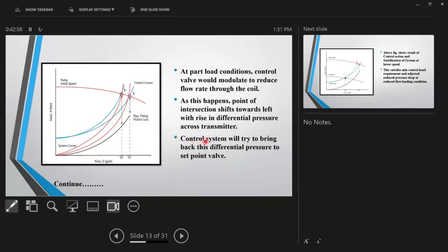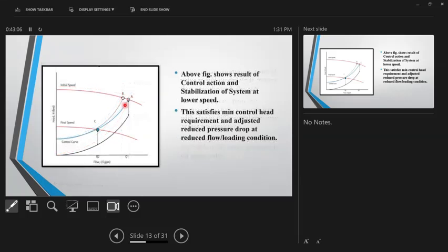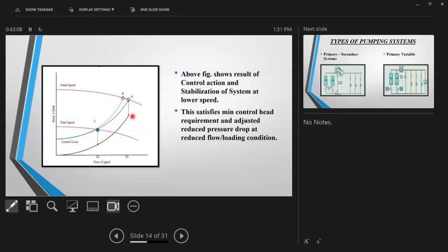But again, we all know the control system will try everything to bring this differential pressure back to set point value. So what it does finally, it does like this. This was our initial point. We thought it would go here, but it can't happen. Now what actually happens is, you remember the control curve, it will follow the control curve, and the final speed will be settled at a point where your flow is satisfied and this distance is equal to this distance. Where that happens, that's the final speed.